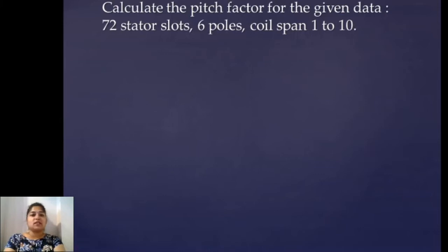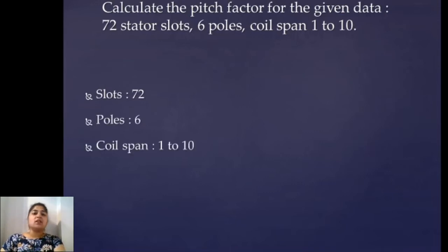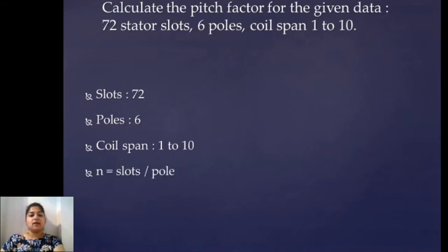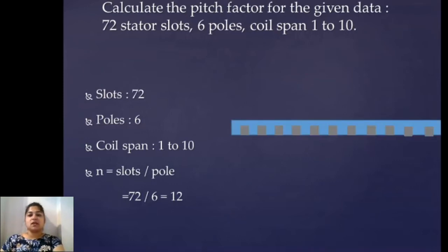Calculate the pitch factor for the given data: 72 stator slots, 6 poles, and coil span is 1 to 10. In a similar way, we write down the slots, poles, and coil span. To check whether the coil is full pitch or shorted, we find N — slots per pole — which comes out to be 72 divided by 6, which is 12. So for a full pitch coil it will be from 1 to 13.